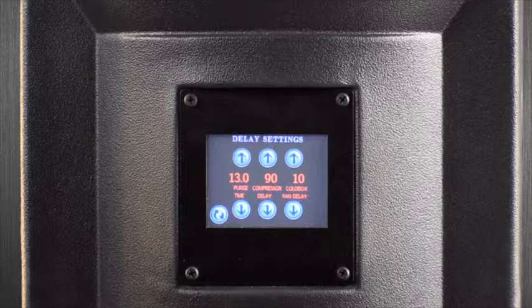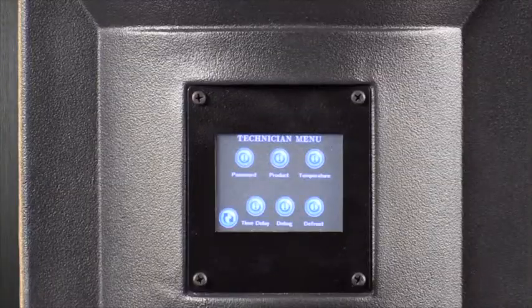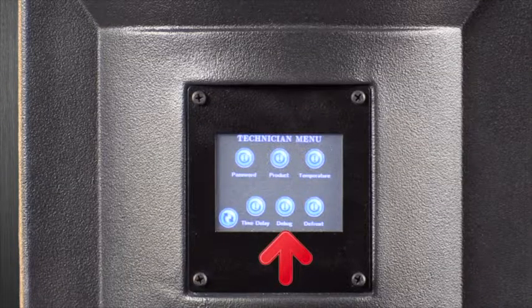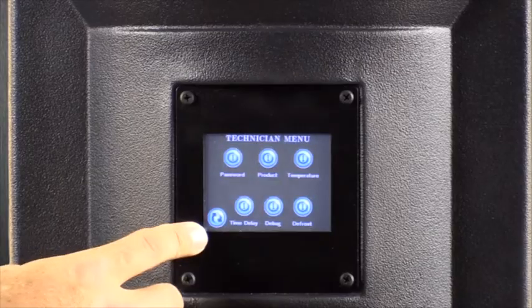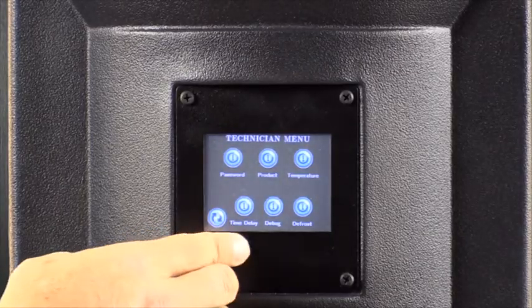The cold box fan delay. This is in addition to the compressor delay: after the original 90 seconds of it being powered up, the compressor will activate, and then an additional 10 seconds after that, the cold box fan will activate. The next icon that you'll notice is the debug icon. Once you've returned back to the main technician menu by selecting the back button located on the lower left of the current screen, now we'll be selecting the debug icon.